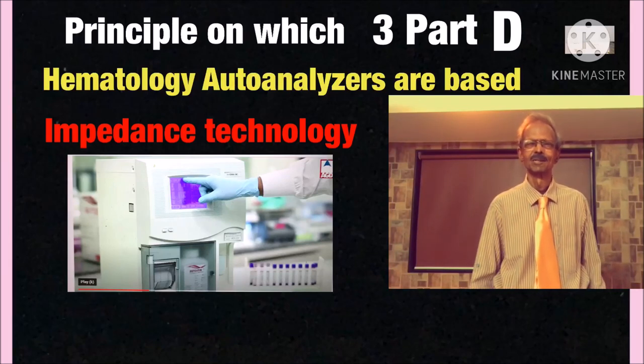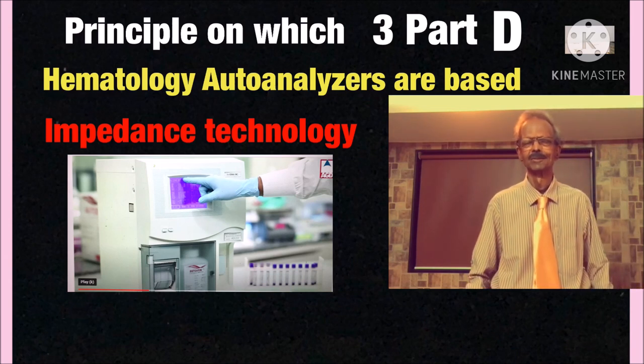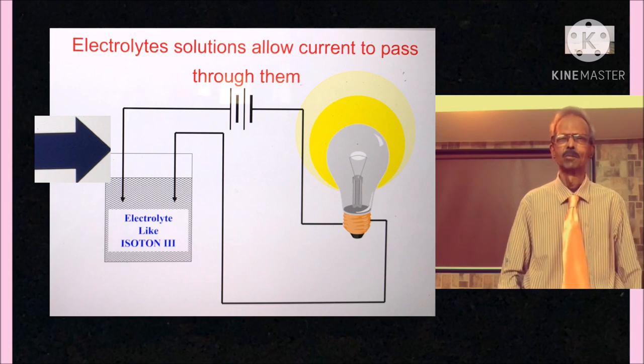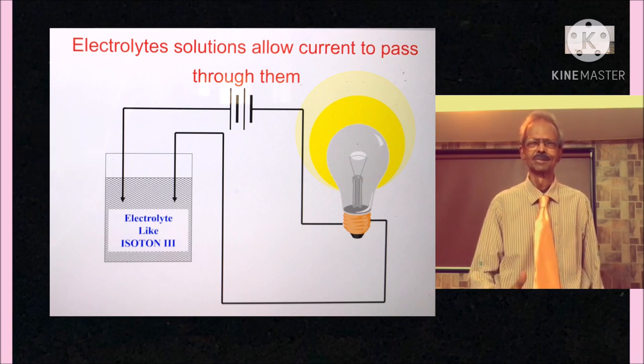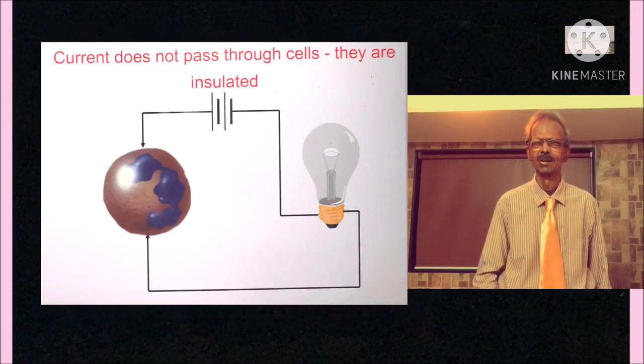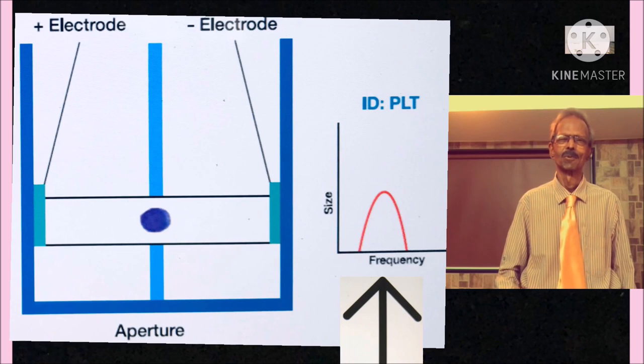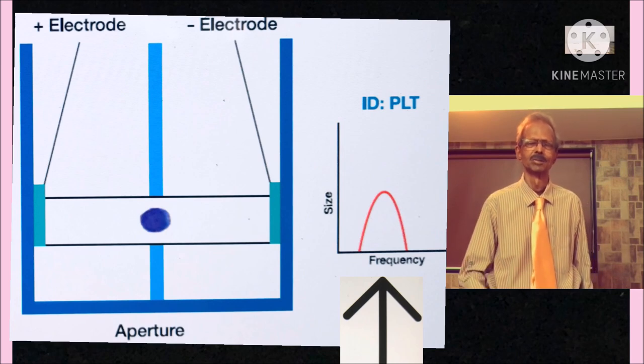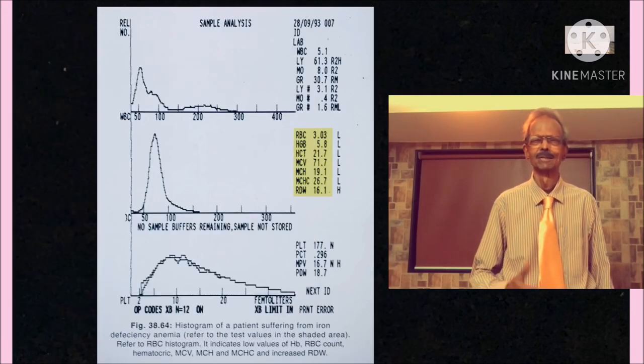Well, principle of three-part differential hematology auto-analyzer is based on impedance technology and this can be explained as follows. If two electrodes are dipped in electrolyte solution and connected, electrical current flows as you can see from the glowing of a bulb. But if a blood cell comes in the way, then current will not flow and impedance, resistance is created which is displayed as a graphic spike as you can see on the left-hand side. Each spike is equivalent to one cell and the area of spike is directly proportional to the size of the cell. Cells are then counted per liter of blood.